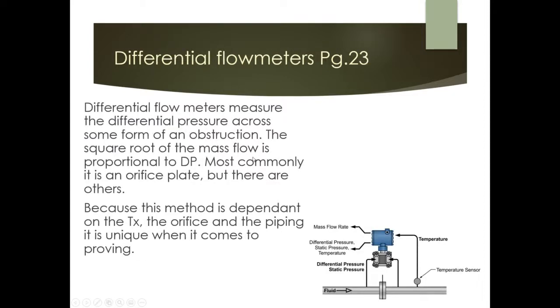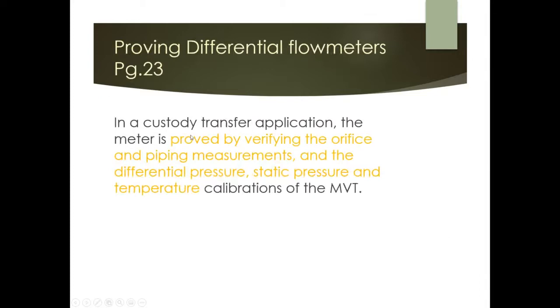Differential flow meters are widely used and measure the differential pressure across an obstruction — usually an orifice plate. The square root of the mass flow is proportional to the differential pressure measured by the transmitter. Because this method depends on the transmitter, the orifice, and the piping, proving is more complex. Orifice plates can wear out, and the transmitter, piping, and orifice itself all come into play.